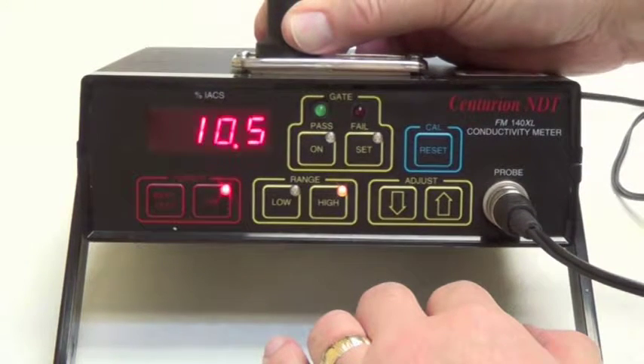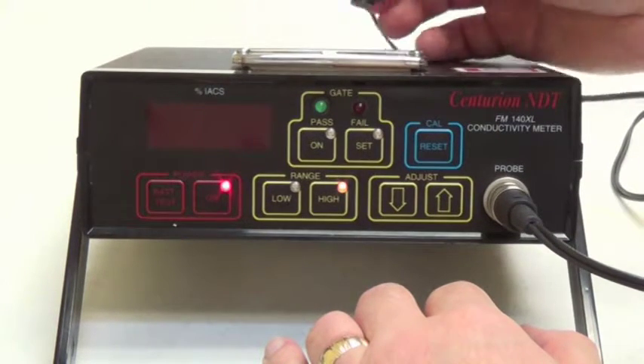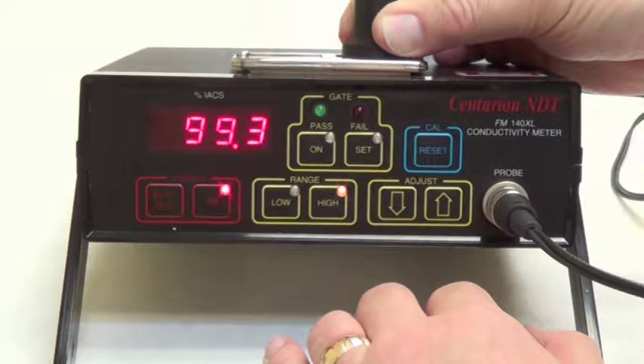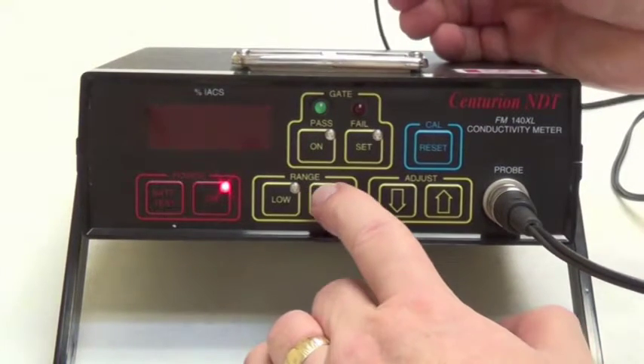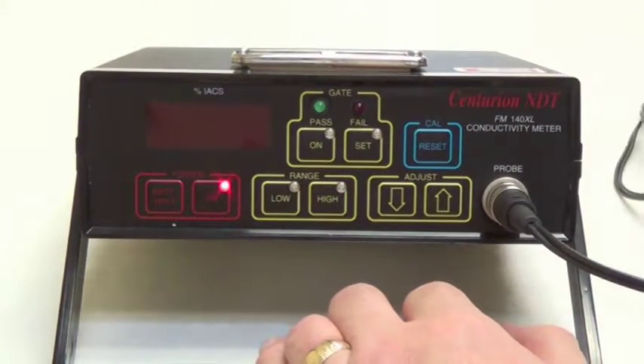Repeat this process until the instrument reads the correct high and low values of the samples. Whichever push button was pressed last must be pressed again such that neither amber LED remains lit. You are now ready to test unknown materials.